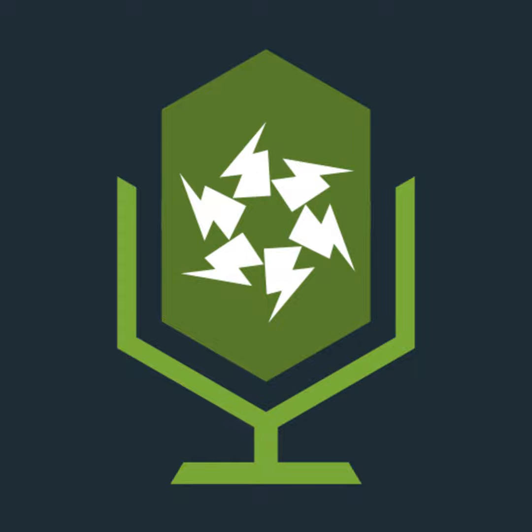Then you have BD4, high density occupation, difficult conditions of evacuation. This obviously is the worst case, such as the tower blocks illustrated here, where there's lots of people, but they have very small paths to exit if they need to exit in an emergency. So there's identifying these different categories, and then there's obviously requirements with regards to wiring systems and cable types for ensuring that they remain operational in a fire condition, and they do not assist with the spread of fire, inhibit the spread of fire.